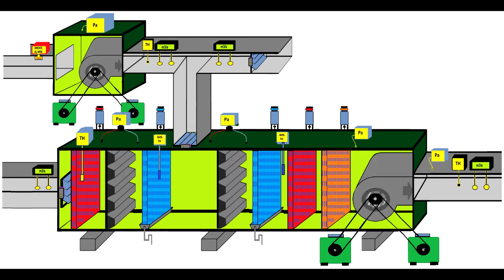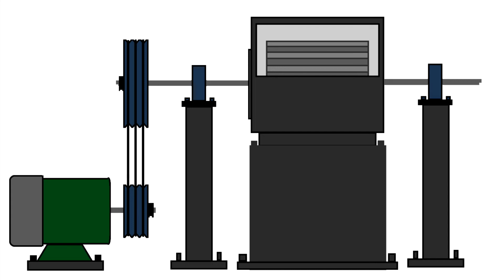Just like the axial one, these belt-driven fans are using belts, and the motors are outside the supply air and the extract air chamber. They have pros and cons, and I will explain to you how these belt-driven fans work. This is the image you will see when you look at the air handling unit from the front. You'll observe the scroll that moves, the pulleys, which are in a cage so people will not get hurt, and the motor, which is outside. This is a great system because this motor is outside, doesn't generate heat inside the supply air chamber, so I don't have to stress the heat exchanger.